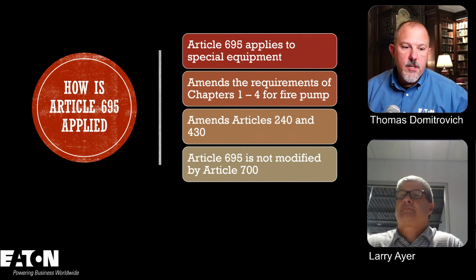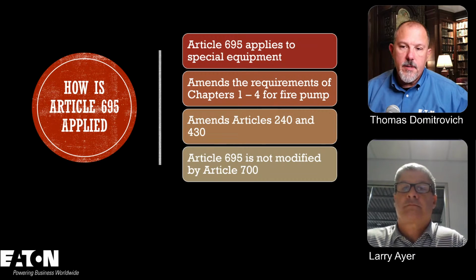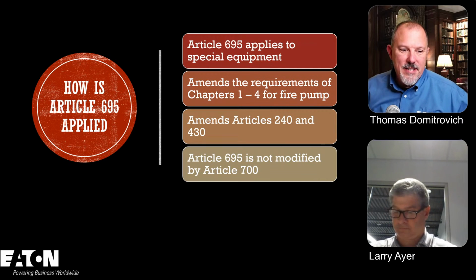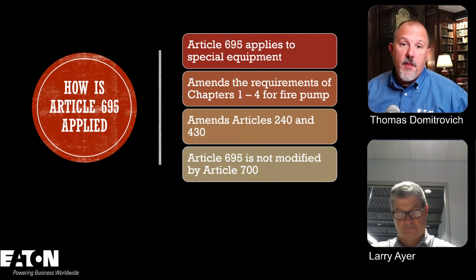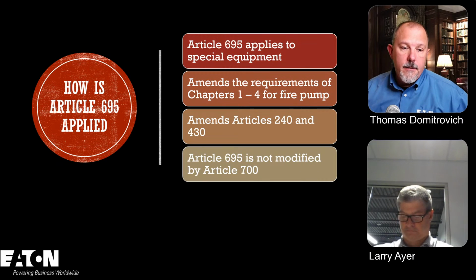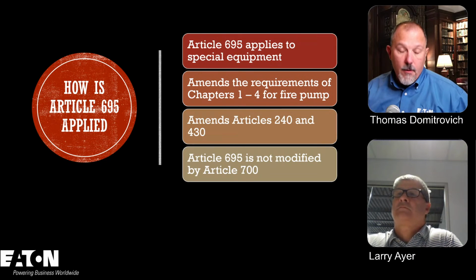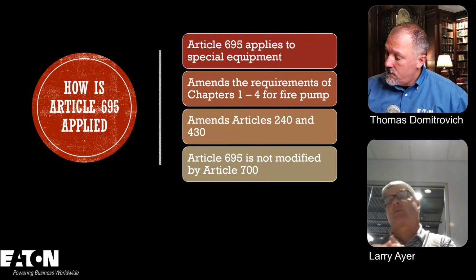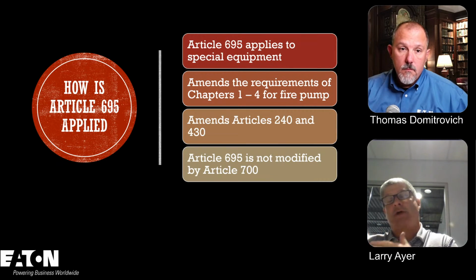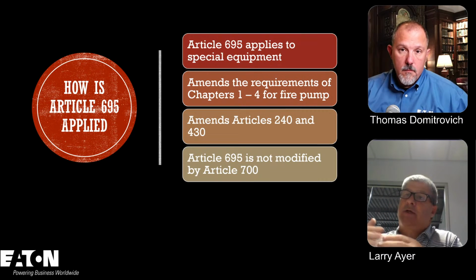Yeah. So to answer Sal Ramirez's question, Salvador, I apologize if I shorten your name, but Salvador's question about the jockey pump, it's for Article 430. And then the controller for that is going to provide the protection and whatnot. So that's all going to be sized and applied based on 430. Now, if you have a transformer in this circuit, and we're going to talk about transformers, you will be supplementing and possibly amending the requirements in 450, right? That's correct, because a lot of times you need primary and secondary overcurrent protection, but we want to limit the number of disconnects we put in the fire pump system, and so that's why we amend that article.